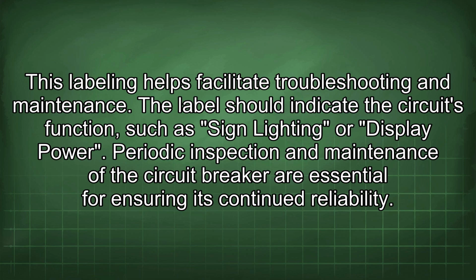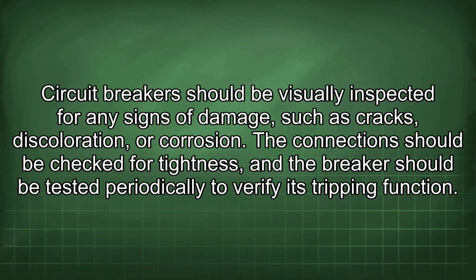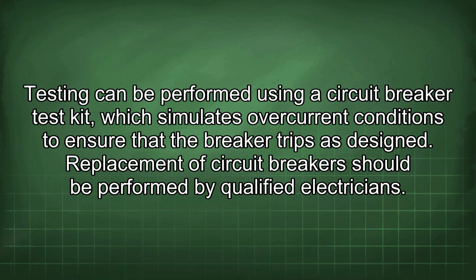Periodic inspection and maintenance of the circuit breaker are essential for ensuring its continued reliability. Circuit breakers should be visually inspected for any signs of damage, such as cracks, discoloration, or corrosion. The connections should be checked for tightness, and the breaker should be tested periodically to verify its tripping function. Testing can be performed using a circuit breaker test kit, which simulates overcurrent conditions to ensure that the breaker trips as designed.